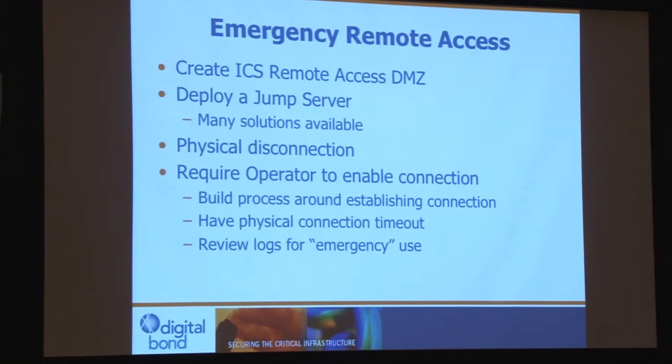So this is just a quick outline of what we typically recommend. We recommend you create a DMZ just for that purpose, just for emergency remote access, and deploy a jump server in that DMZ. So basically, when someone is trying to access the network, they will connect to this jump server, and from that jump server, they will be allowed into the control system. But once you have this set up, you then physically disconnect it. So it's not operational, it's down.